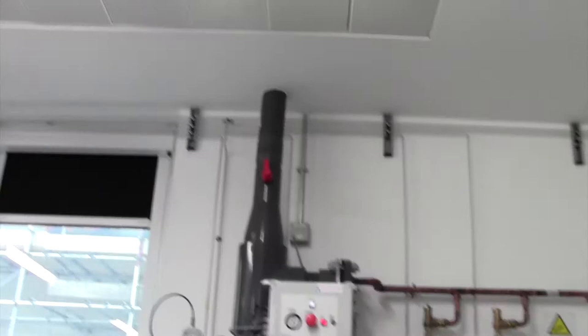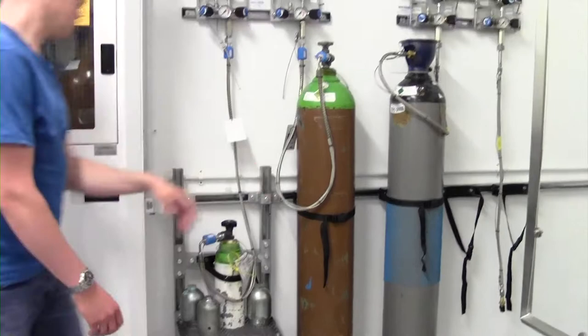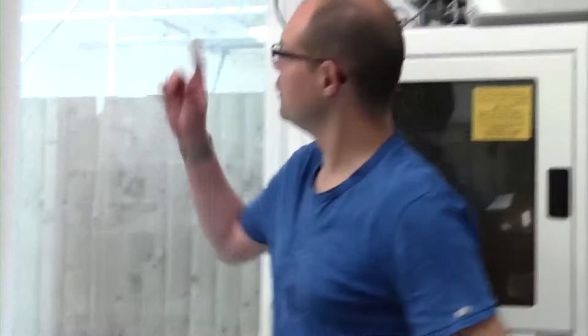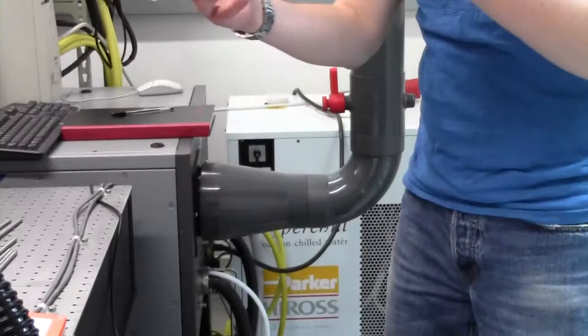We take it out through these lines. We add onto it Krypton. It's only a small bottle. Krypton's very, very expensive. We also put in an extra balance of helium, which is a big bottle. The last thing we do is we add in a little bit of neon, which is there. So, these four gases flow around our pipes and into the back of the laser. The laser can control the concentration of a mixture of those gases together. And they sit there in that chamber.